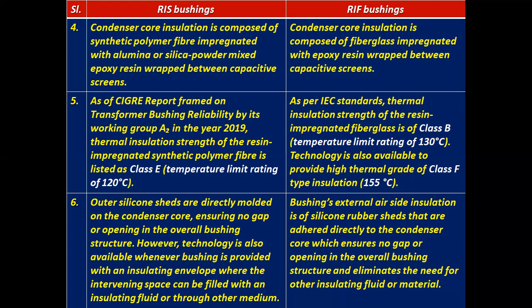But in the case of RIF bushings, the external airside insulation is of silicone rubber sheds that are adhered directly to the condenser core, ensuring no gap or opening in the overall bushing structure and eliminating the need for other insulating fluid or material.